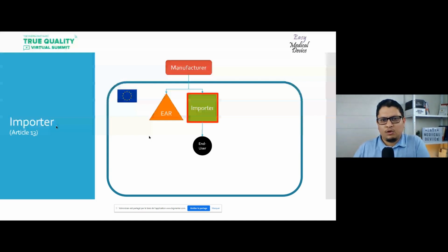He has also the right to say, no, I will not distribute this product because it's not compliant. And it's not only the right, he has to do that. It means that he has the responsibility to say, yes, I confirm this product is okay. And to confirm that the product is okay, he's placing a label, his label, on the product, to say imported by this company. And the label for me means like a release, so the product is released, so it's fine.